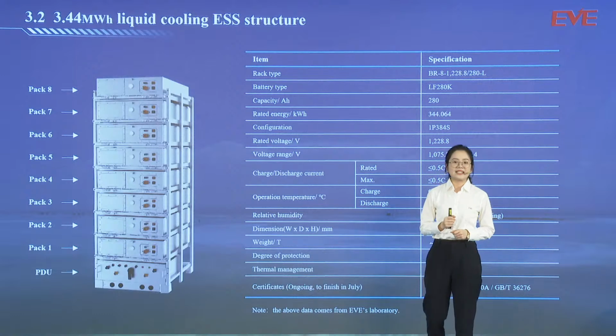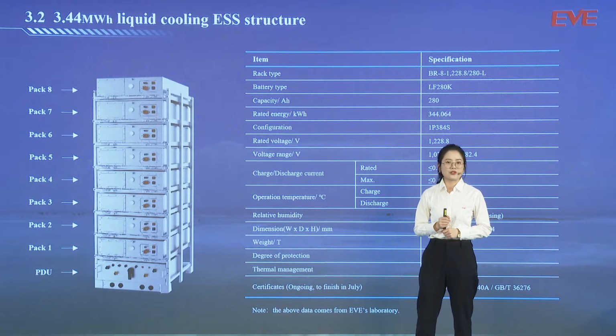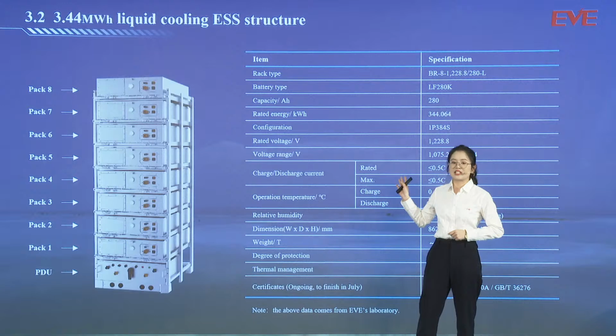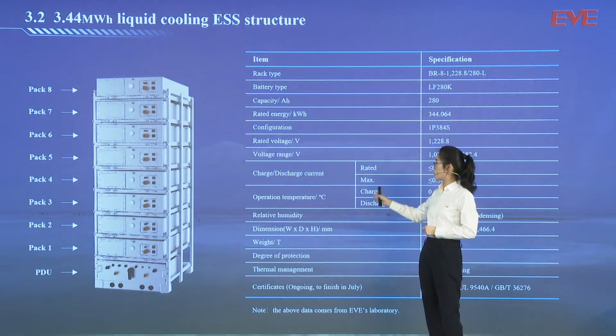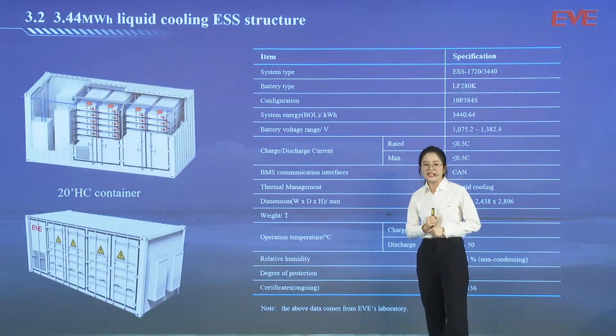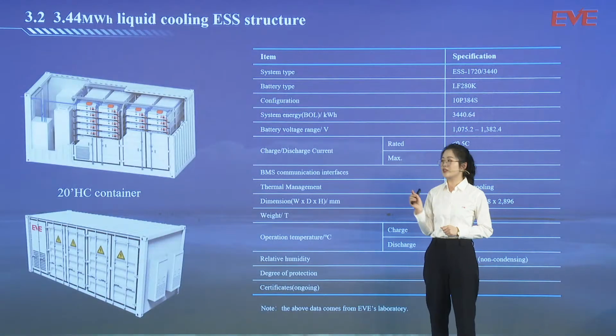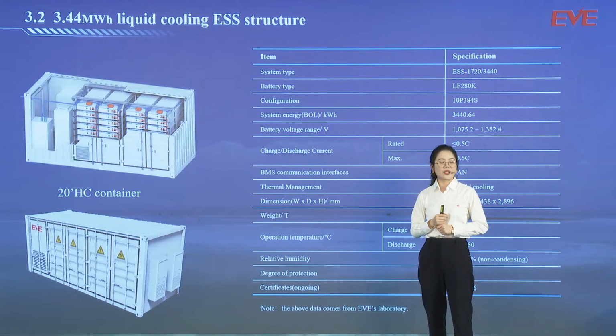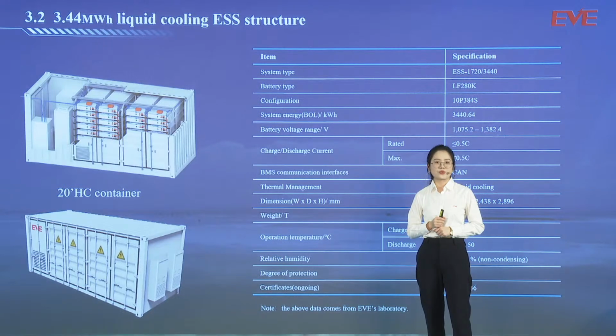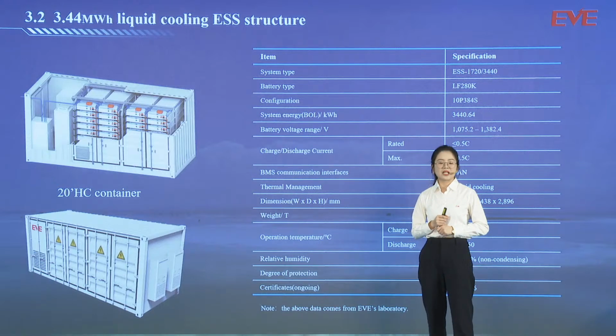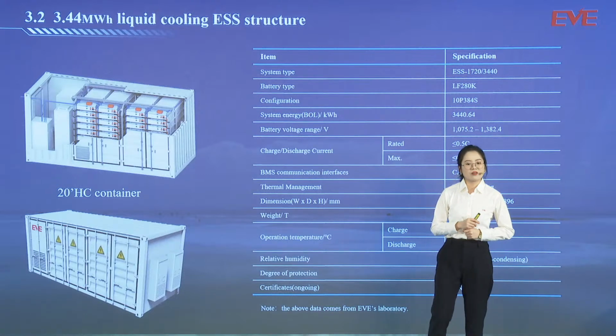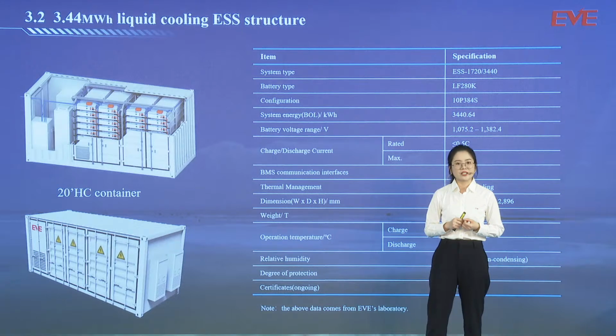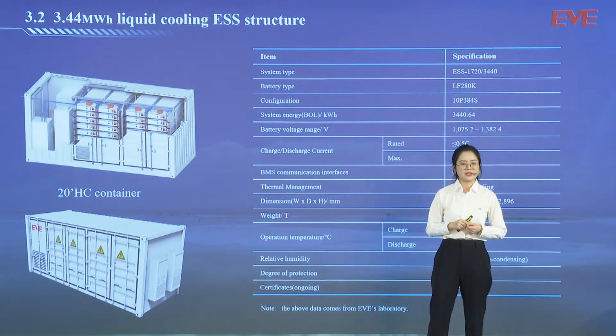We stack 8 battery packs in series into a 280 ampere-hour, 1228.8 volt rack, shown here together with the PDU. 10 racks are installed in parallel in the container. A standard liquid cooling 20-foot high container can hold up to 3.44 megawatt-hour of battery capacity, doubling the capacity compared to an air cooling solution with the same cell. It also offers low cost, good heat dissipation, and small temperature rise difference.